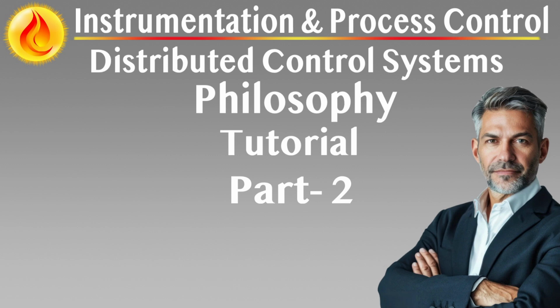Seamless but independent integration. While ESD systems communicate with the Distributed Control System (DCS) for monitoring, they remain functionally independent. Critical shutdown actions are executed through hardwired circuits to actuators, independent of DCS logic, ensuring that control failures cannot affect safety responses.